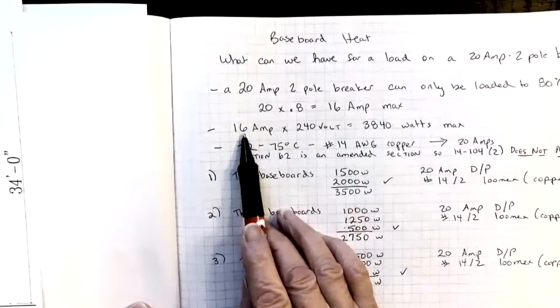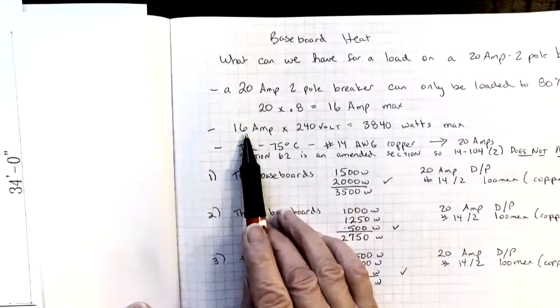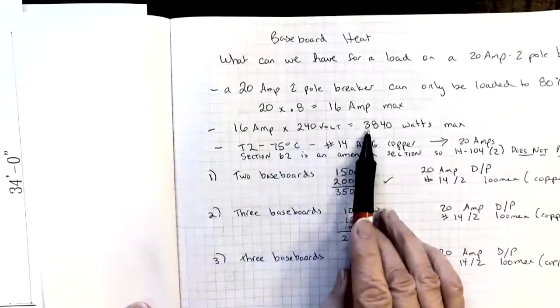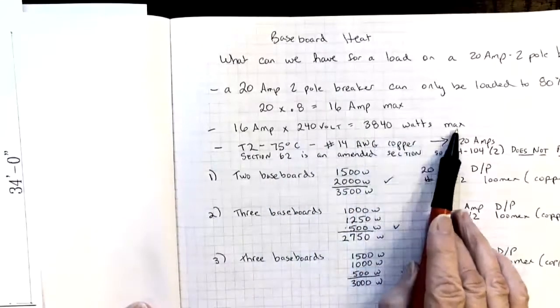When we use watts law, amps times volts, we can figure out the maximum number of watts that we can put on that 20 amp breaker. So 16 times 240 will give us 3840 watts max.